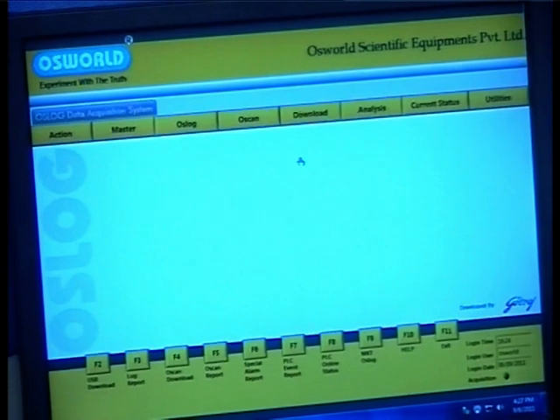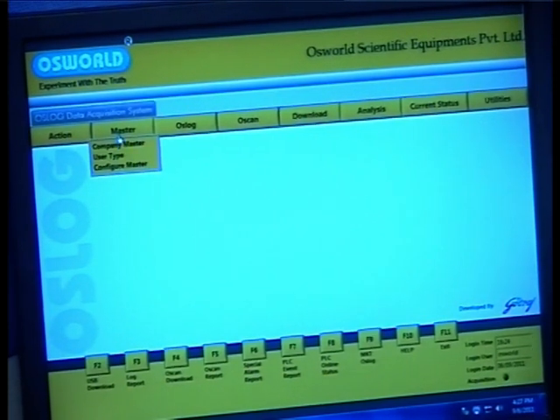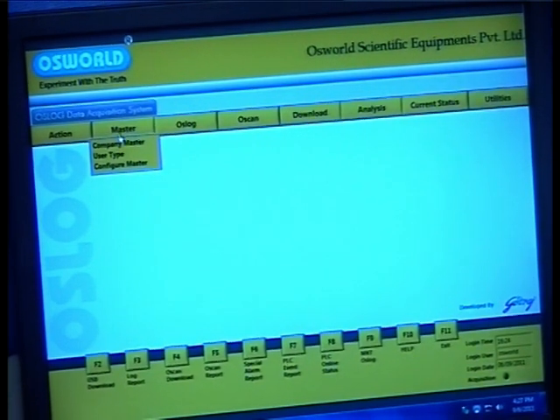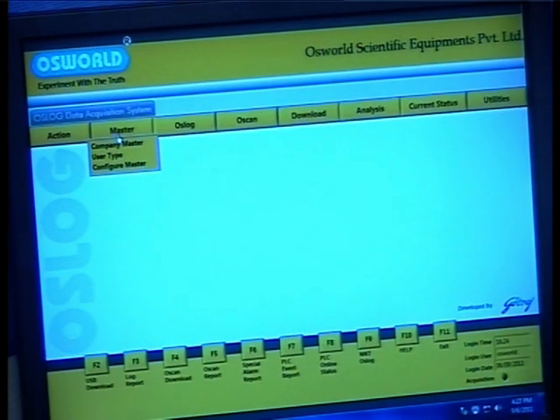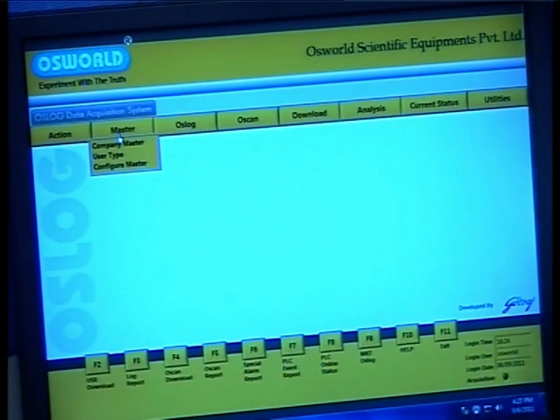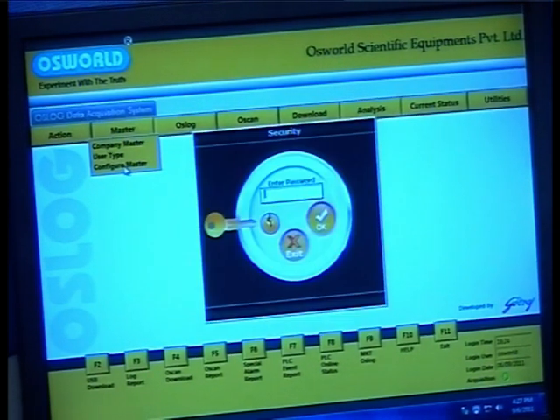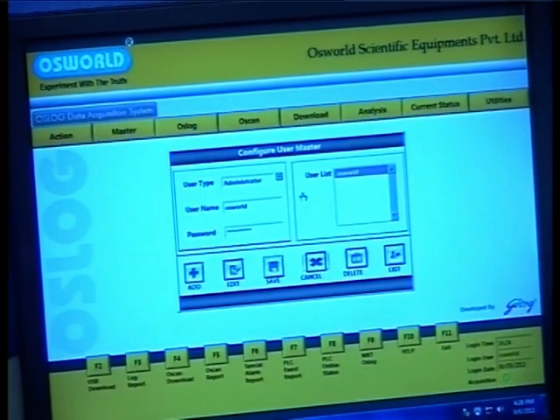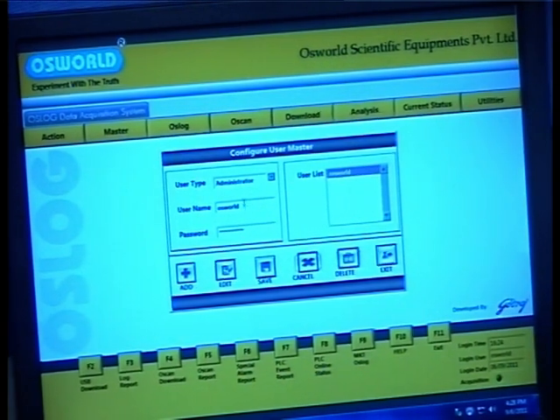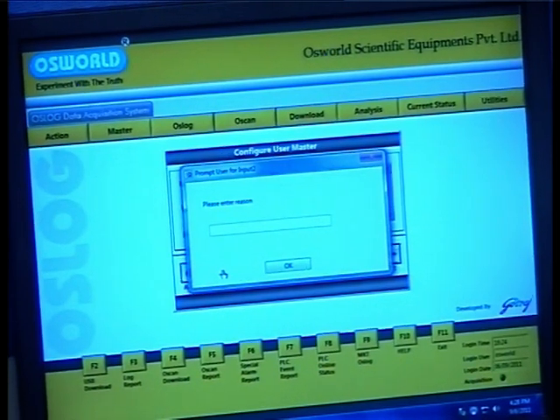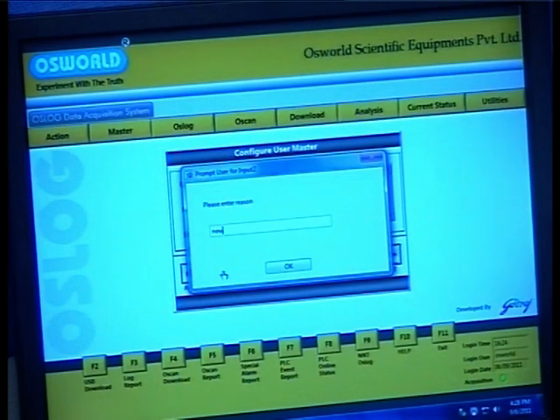I will now show you how to add a new user or delete a user from the system. Since the software is accessible by multiple users, you would need to configure the user ID and password of a new user to enable access for them. Go to the master drop-down, click on the configure master tab and enter your password. A configure user master window opens up. Click on add — you will observe another window requesting for a reason to add this new user. Information entered here is stored and can be viewed later in the audit trail report.